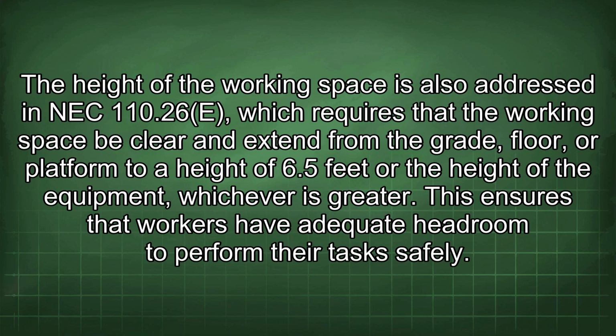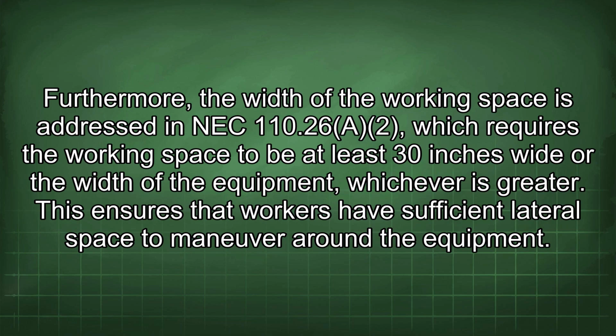The height of the working space is also addressed in NEC 110.26(E), which requires that the working space be clear and extend from the grade, floor, or platform to a height of 6.5 feet or the height of the equipment, whichever is greater. This ensures that workers have adequate headroom to perform their tasks safely. Furthermore, the width of the working space is addressed in NEC 110.26(A), which requires the working space to be at least 30 inches wide or the width of the equipment, whichever is greater. This ensures that workers have sufficient lateral space to maneuver around the equipment.